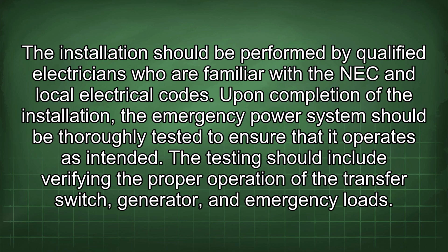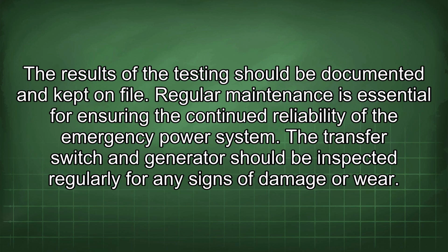Upon completion of the installation, the emergency power system should be thoroughly tested to ensure that it operates as intended. The testing should include verifying the proper operation of the transfer switch, generator, and emergency loads. The results of the testing should be documented and kept on file.